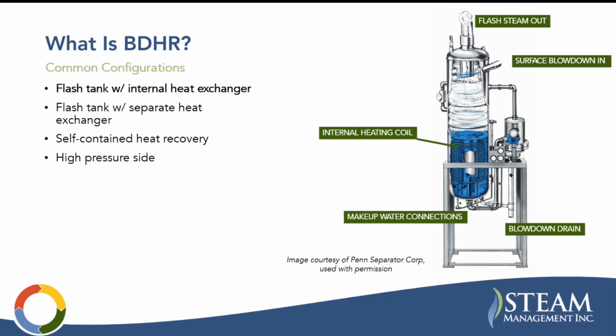Some common configurations. So these are just different examples of unit designs. There's different manufacturers of each. These are just examples, but I will say Penn Separator was kind enough to give me some information, as well as Alstrom. So I appreciate that. But this first example is a Penn Separator unit that's a flash tank with an internal heat exchanger, like what we just looked at. Basically, your makeup water here is in this coil. We just talked about that. And basically, the heat exchanger is submerged within the tank. So that allows heat from the hot blowdown liquid to be captured.